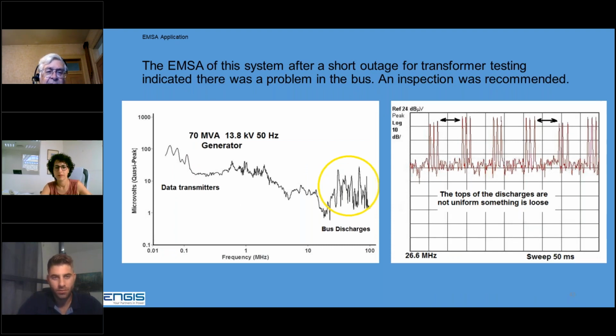This is at a nickel smelter in the Dominican Republic. Again, this is the amplitude. This is the frequency. It's a fairly small generator. They ran off of a chemical compound that they produced with a little refinery there. And here's the bus discharges. Not that strong, but definitely something going on. When we looked at the pattern at 26 megahertz, which is the spike right here, here's what the pattern looks like. Notice the top of the discharges are not the same. I've got 3 discharges per positive and negative half cycle. The tops are not uniform. That tells me something is loose.